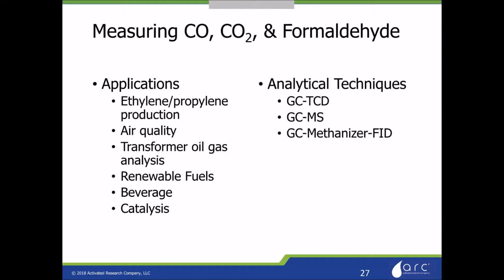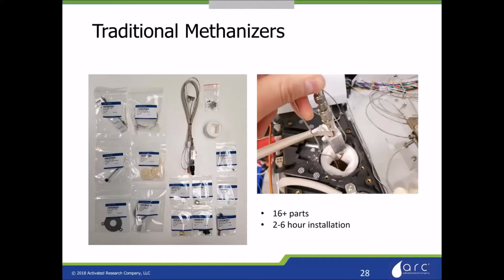So we have a number of customers who've used nickel catalysts and poisoned them often, especially in the transformer oil gas analysis area, where small amounts of sulfur can poison the methanizer and render it useless. So the traditional methanizer, as I mentioned, has a lot of tubing in and out, fittings that can become difficult to remove, and over 16 parts with a 2 to 6 hour installation.